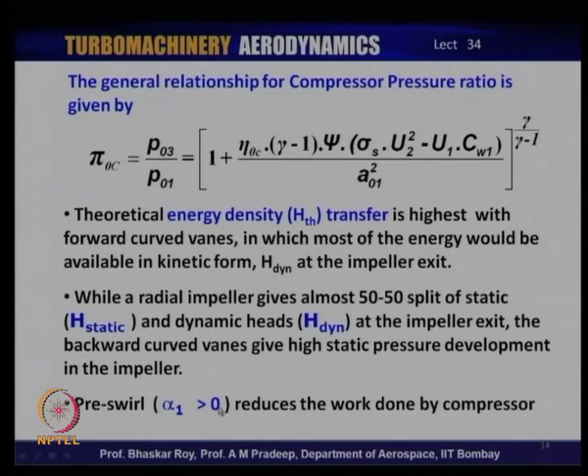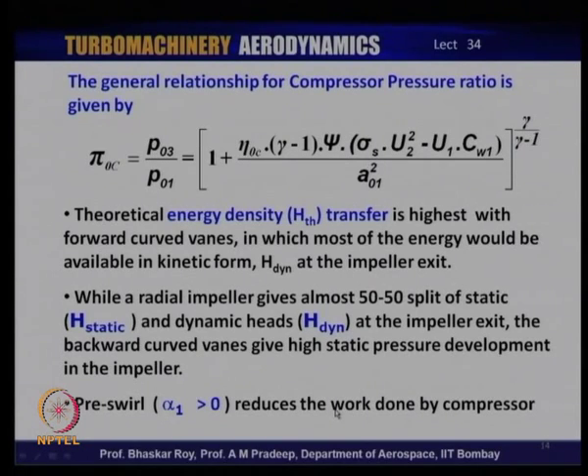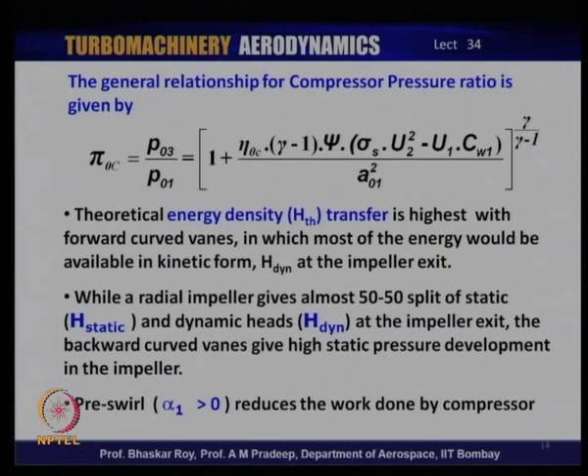Backward-curved vanes give very high static pressure development right in the impeller itself, especially with the advantage of splitter vanes. The pre-swirl — using inlet guide vanes in front of the rotating impeller — reduces the work done, but avoids supersonic speeds at the impeller eye inlet and avoids all kinds of separation, shock boundary layer, and separation-related issues right at the impeller eye. So it is a useful thing to have if you need it — but you have to decide whether you need it or not.